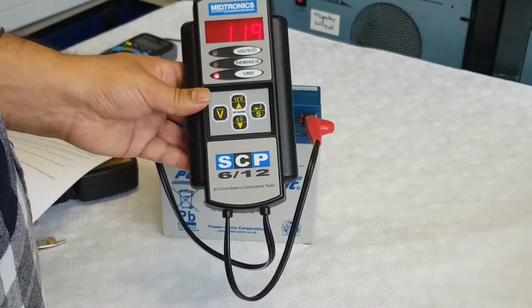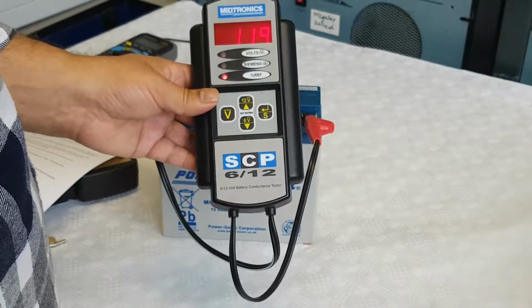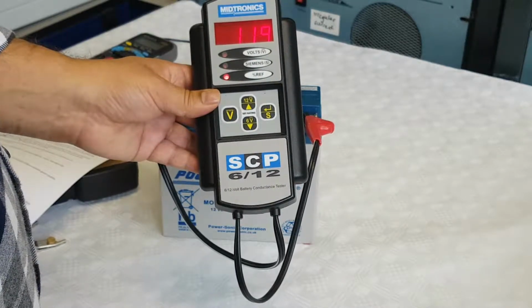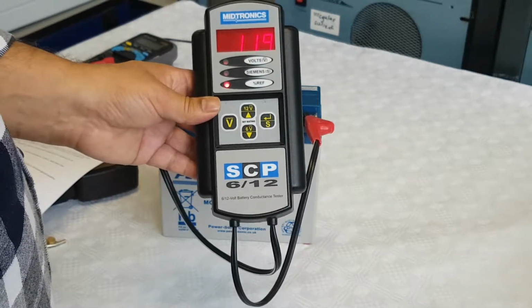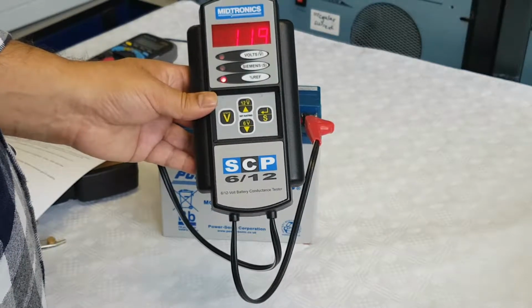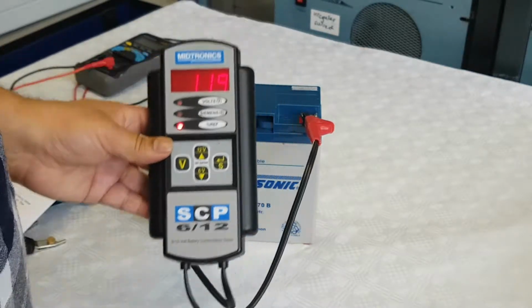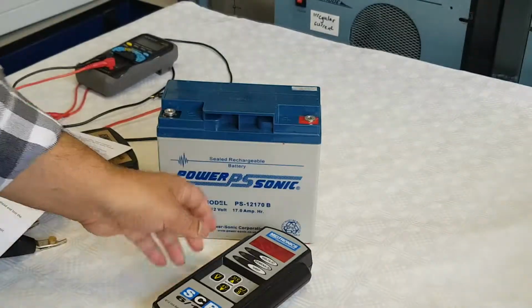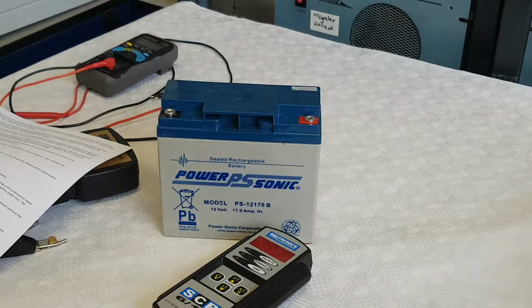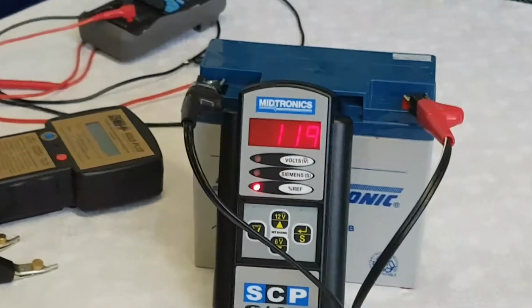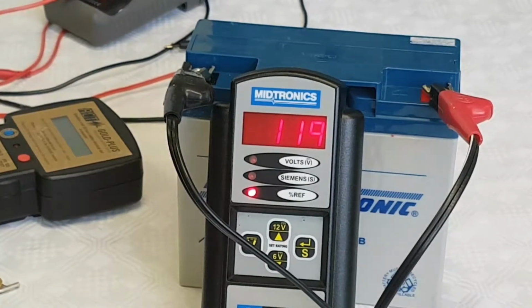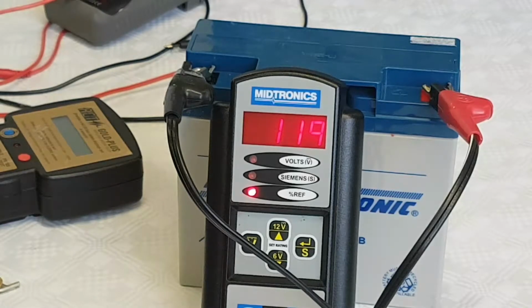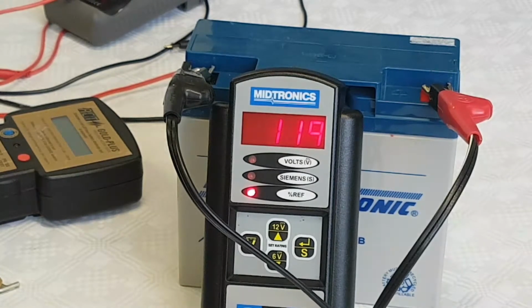So the percentage conductance is 119%, which indicates that the battery is good quality. It hasn't reached its end of life, and it's not defective. Okay, the Midtronics test has indicated a relative conductance value of 119%, which indicates that the battery isn't defective and it hasn't reached the end of its service life. The battery therefore doesn't need replacing.